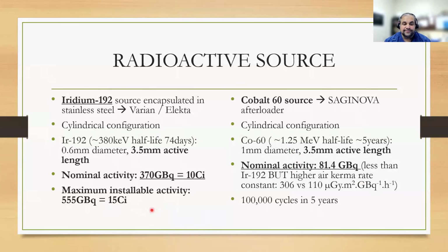Now with the new Bravos, and I believe even with the Flexitron afterloader, the maximum installable activity for your radioactive source can go as high as 15 curies. So for clinics that do a lot of brachytherapy or anticipate doing a lot of brachytherapy, this is really beneficial. For clinics that cannot do the constant source exchanges required by iridium 192, where typically the source exchange is done every 3 months, cobalt 60 comes in handy because of the half-life over here, 5 years. So a source exchange is required every 4 years or so.